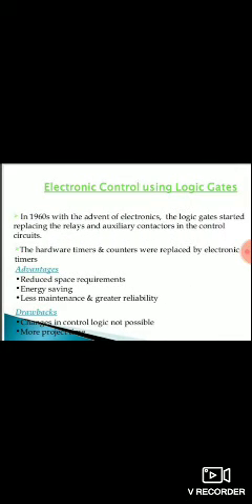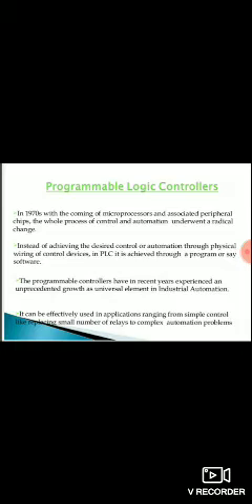Electronic controller using logic gates. In the 1960s, with the advent of electronics, the logic gates started replacing the relays and auxiliary contactors in the control circuits. The hardware timers and counters were replaced by electronic timers. Advantages: reduced space requirement, energy saving, less maintenance and greater reliability. Drawbacks: change in control logic not possible, more project time.